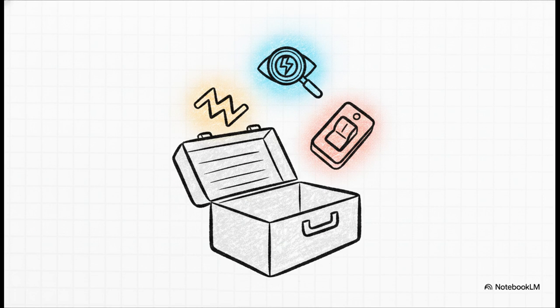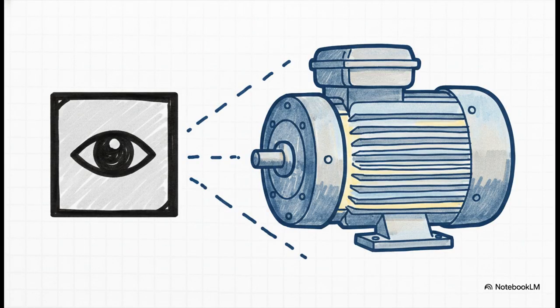Huge win. Up to this point, we focused really heavily on plant-wide protection, the entire switchboard and generation network. But what happens when we zoom all the way down to a single critical asset? Next time, we are going to dive deep into the numerical relay that stands guard over individual large motors, the SPM150C. We'll unpack how one tiny aluminum box keeps a massive motor from burning itself to a crisp.